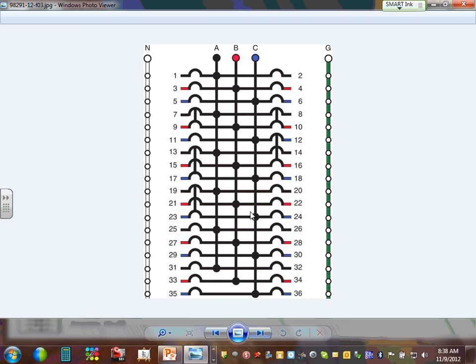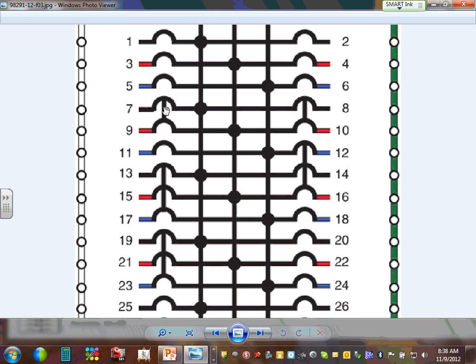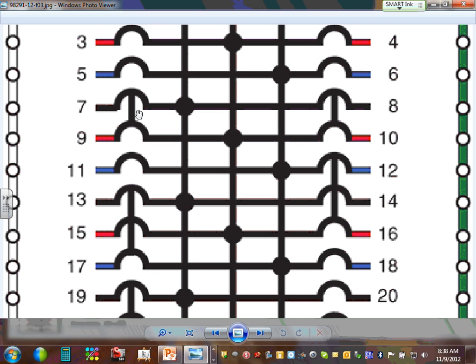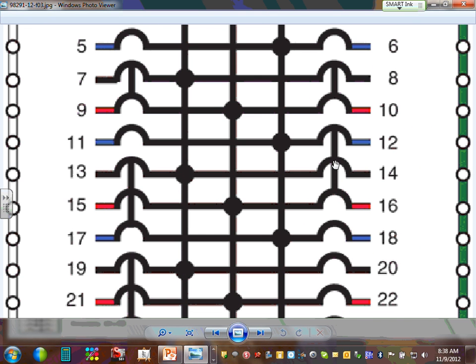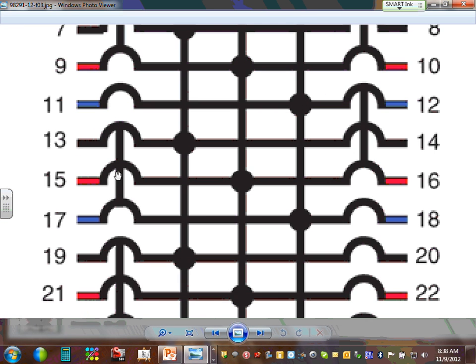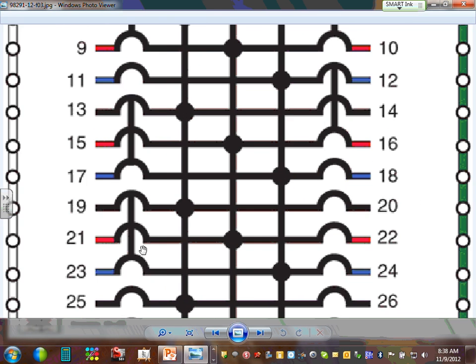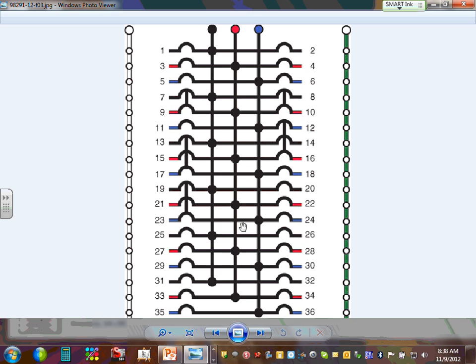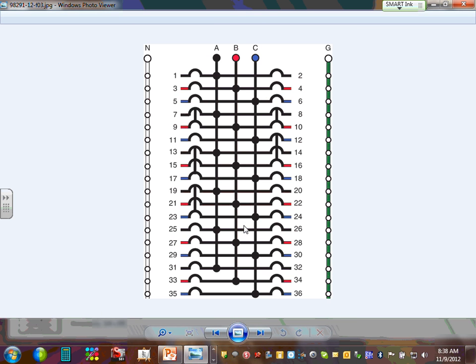Okay, here's another panel. Can you guys see how they take two circuit breakers, 7 and 9? That's 2 hots, 208, 2 hots, 208. This is how you take 3-phase, 12, 14, and 16, 3-phase, 13, 15, and 17, 3-phase. Can you guys see how they circuit out of these? That's exactly what you've done with your friend Chad. Can I have thumbs up, Chad? Cool.